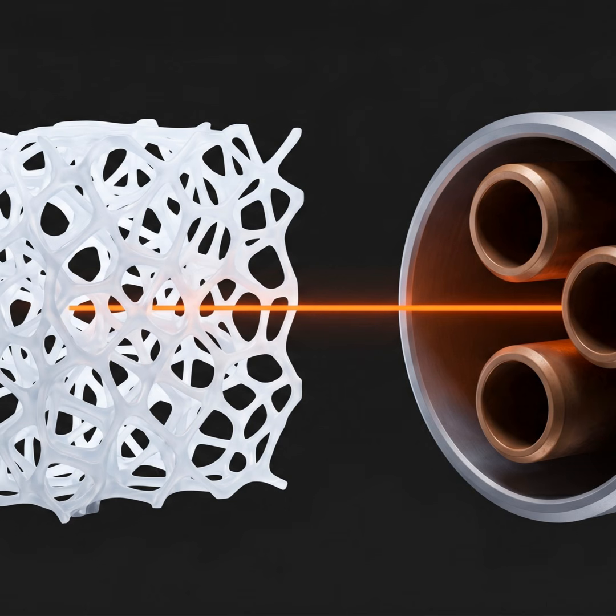You install industrial telemetry sensors directly onto the skid, clamp-on ultrasonic flow meters and precise temperature probes. These feed data into a lightweight software layer that calculates the exact mass flow rate and temperature differential, down to the decimal point, the exact thermal energy in BTUs that your skid is transferring into their water system. You're meticulously metering the heat transfer in real time.